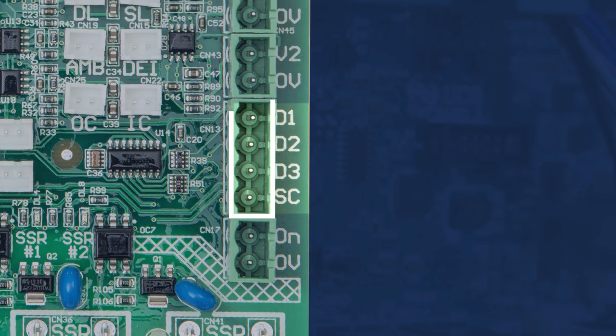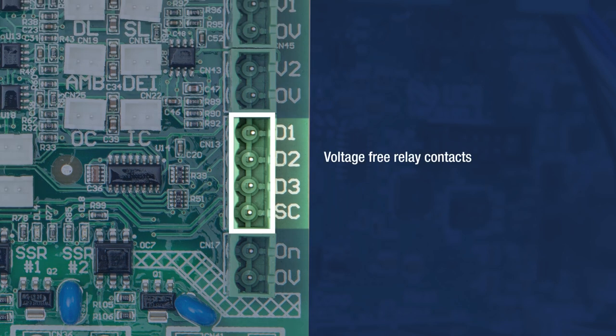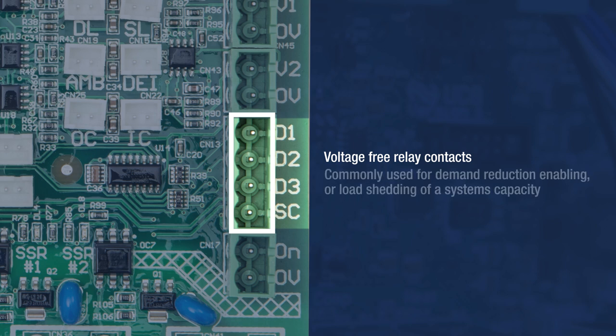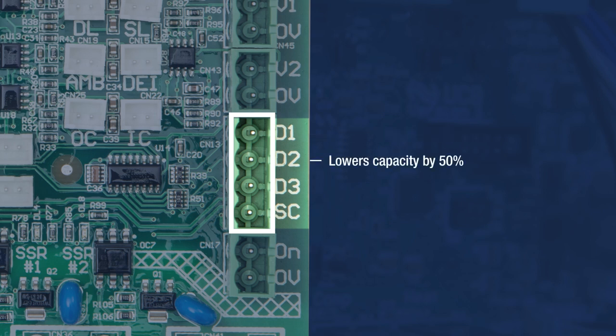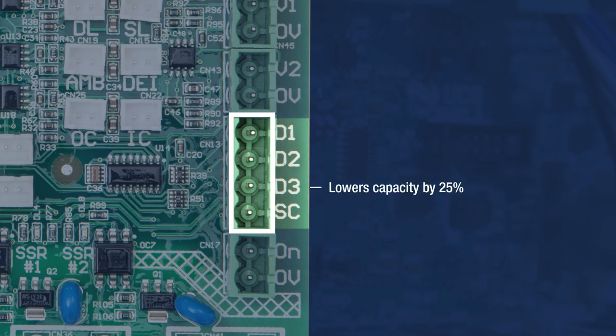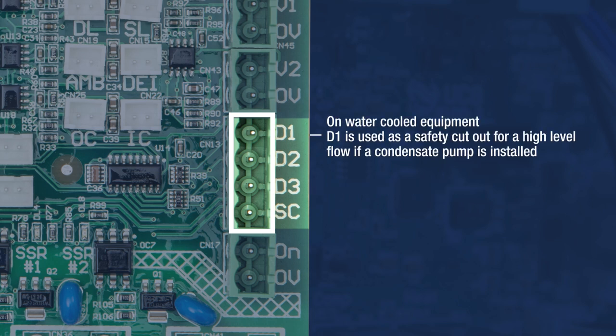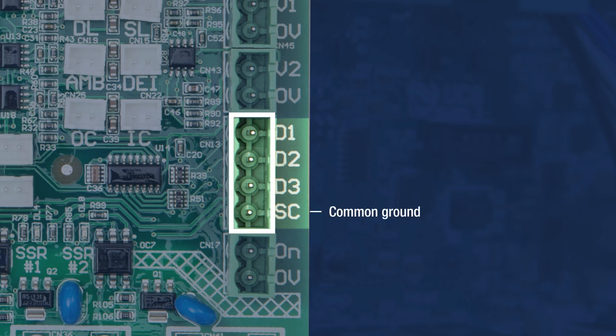D1, D2, D3, and SC are voltage-free relay contacts commonly used for demand reduction, enabling, or load shedding of a system's capacity. D1 activated switches the compressor off and the indoor fan is allowed to run. D2 activated will lower the capacity by 50%. D3 activated will lower the capacity by 25%. On water-cooled equipment, D1 is used as a safety cutout for a high-level float if a condensate pump is installed. SC is the common ground terminal for these inputs.